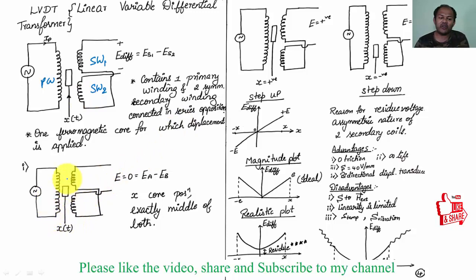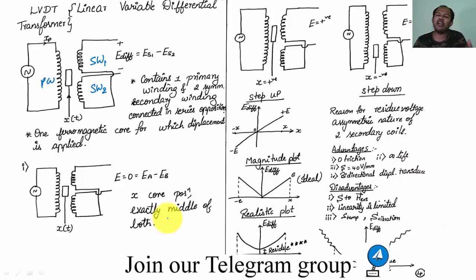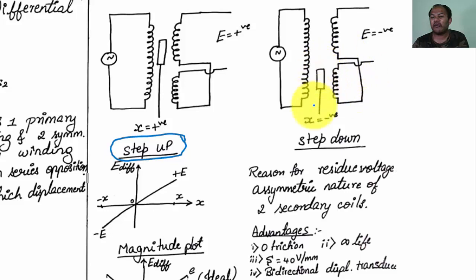When the ferromagnetic core is exactly in the middle, there is no displacement and EA equals EB, giving EMF output equal to zero — the core has not displaced forward or backward. When the core moves upward, ES1 is greater than ES2 and you get a positive output voltage, acting like a step-up transformer. When the core is pulled downward, ES1 is less than ES2 and you get a negative output, acting like a step-down transformer.